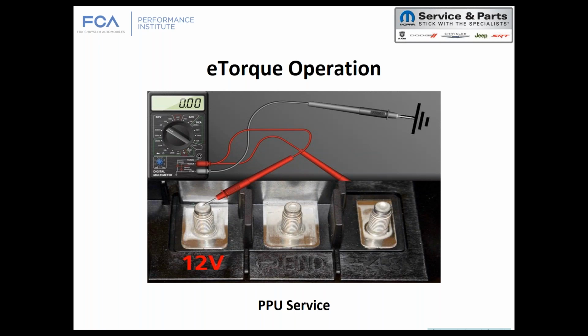If the contacts in this contactor have welded themselves together, it is possible, and it is a fault, that the 48 volt post will still show 48 volts, or the 12 volt post will still show 12 volts if the contactors have welded themselves together.